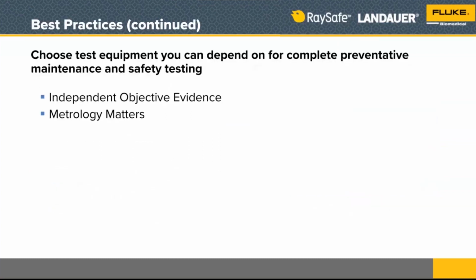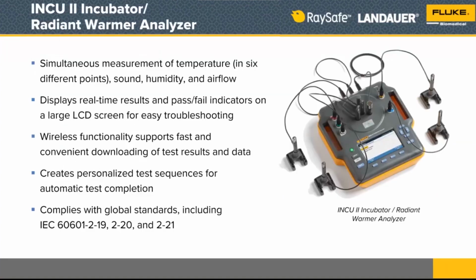Choose test equipment you can depend on. And the metrology matters here. We'll talk about that in a different topic on a different day. Here are some attributes that you might want to consider. Simultaneous measurement of parameters. Displays real-time results, pass and fail, when you're doing the standards-based tests. Wireless functionality for some countries. Not every country in the world allows wireless communication between your computer and the test instrument, but we have a range that do. Ask your representative to help you with that. And you can create your personalized test sequences. We comply with 60601-2-19, -20, and -21 for infant incubators, radiant warmers, and transport incubators.